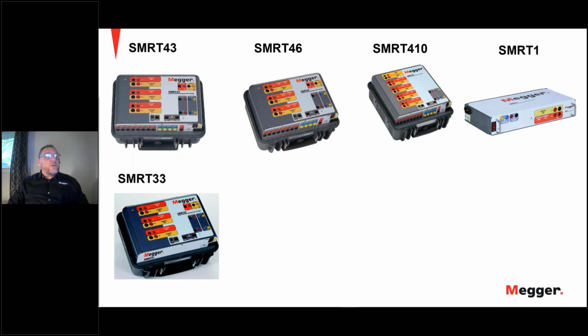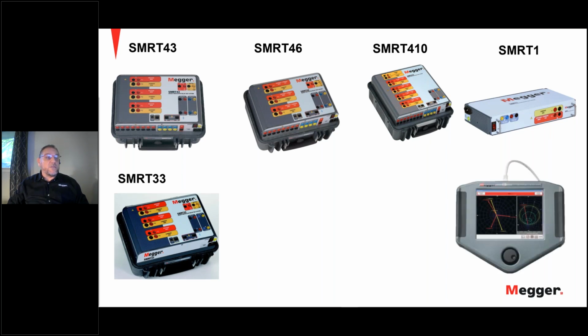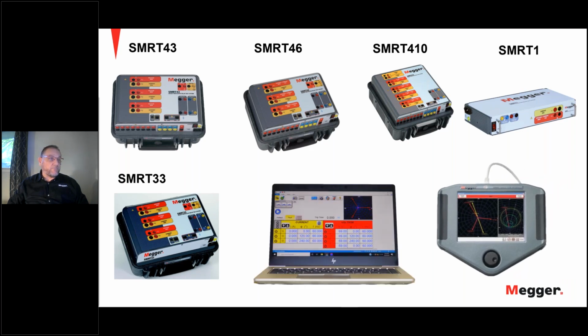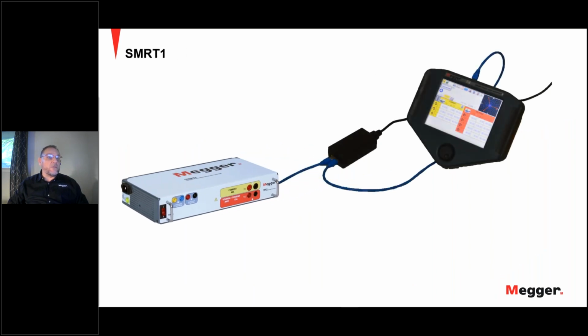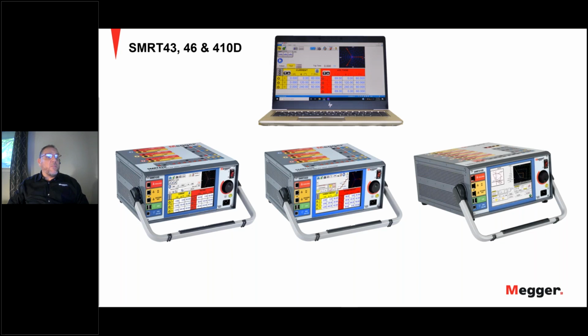So all of these units in the clamshell and the SMRT1 can be controlled either via an STVI, which is the Smart Touch View interface, or via a PC. Now, the same software that you can install on your PC will run on the STVI. So you've got full control of the units with any automated test module that was created. As for the SMRT1, if you use the STVI on the SMRT1, you will need a power over Ethernet adapter to power up the STVI to be able to control the SMRT1. Moving on to the display units, apart from the onboard display that you've got on the units, you can also control the unit from the PC, similar to the other units that I've already mentioned.